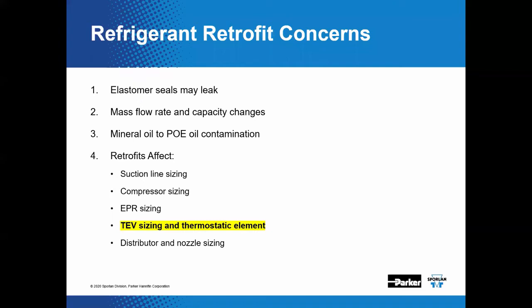During a retrofit project for refrigerants, there are many concerns. If we take a look at the slide here, you'll see things like concern over elastomer seals that may deteriorate and leak. Mass flow rate and capacity may change. Mineral oil to POE oil or lubricant contamination may occur. Retrofits likely affect suction line sizing, compressor sizing, evaporator pressure regulator sizing, thermostatic expansion valve and distributor selection, and even thermostatic element selection. Any one of these listed concerns could be the subject matter for a complete webinar in and by itself.